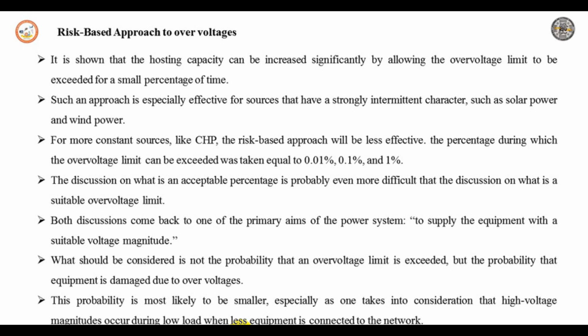So what needs to be considered is the probability that those customers experiencing high voltage have sensitive equipment connected, in which high voltage will occur. A discussion on the use of a risk-based approach should again involve all the stakeholders, where an important point of discussion should be who actually carries this risk. If network operators get a fine when the over voltage limit is exceeded, a worst-case approach using a safety margin will likely be used. When a fund is created to pay for the damage to equipment due to over voltage caused by distributed generation, this will encourage the network operator to allow more distributed generation to be connected.